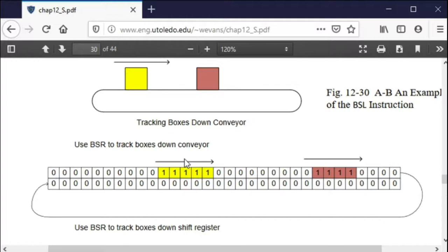And you say, is this ever used? It's used a lot. This technique is used a lot for tracking of product. I used it in a program in 1980 for tracking of the product of a woven fiberglass and spools, going down in a tote with a barcode. And so this one's going to this country, or this area. This is going to this area. And there were 19 side conveyors. And they basically just stacked up based on the barcode. So you read the barcode, go down, and transfer at one of those 19 points. It worked great. So we had to have 19 shift registers to do that.